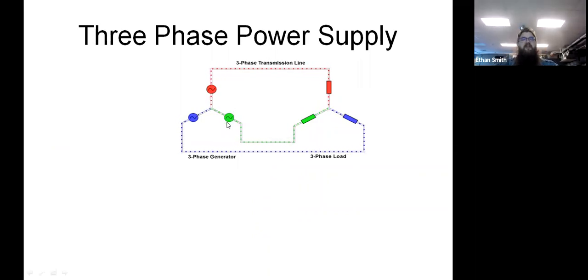We take what's called a three-phase generator, which is simply a giant three-phase motor, meaning it has 3 windings in it. We'll look a little closer at some three-phase motors here in a minute. And we rotate a magnetic mass inside those 3 coils of wire. Anytime we have a rotating magnetic field, moving that magnetic field through wiring, we're going to get induced voltage. We have a little demonstration of that.